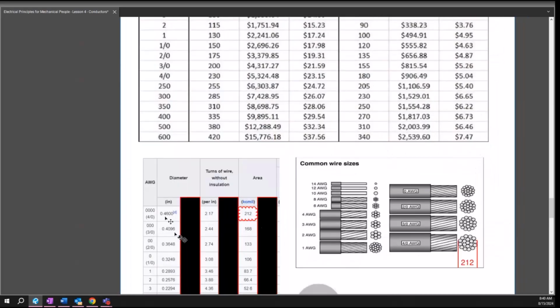It's '4 aught.' Following that KC mil concept, when you get into the actual KC mils, like 250, that's 250 KC mil, 300 KC mil, and so on. The KC mil continues increasing, and that's how you go from number 1, to 4/0, to 350 KC mil—that's how you say that. Yes, it is slightly confusing. There's a whole lot of reasoning behind that, but that's just the high level basics.